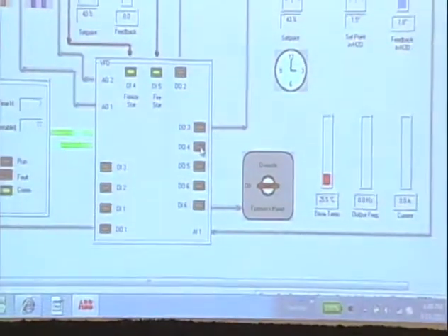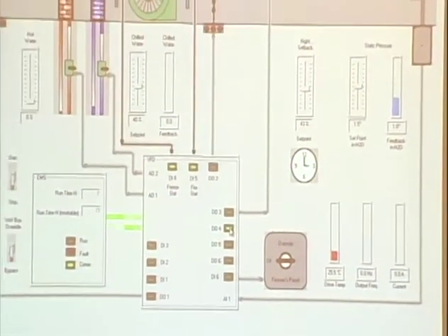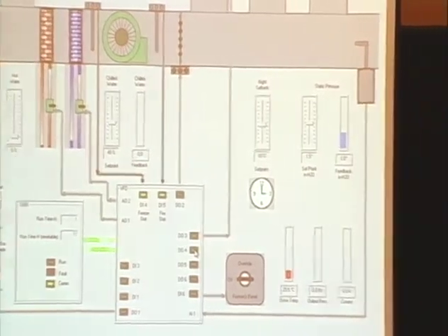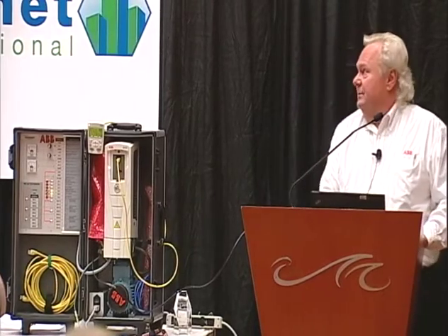Okay. So in 98, we realized we've got these relay outputs and analog outputs that we're not using in HVAC. Why don't we expose them to the building automation system? So if you look on the demo case here, I'm going to fire relay output 4. Now the drive's not even running right now, but as long as I've got power on the drive, I can fire relay output 4, and the little light should have come on the front of the demo case. So anytime this drive's running, I want to start an exhaust fan. We can do that. You can use the contact output from our drive to start the exhaust fan.